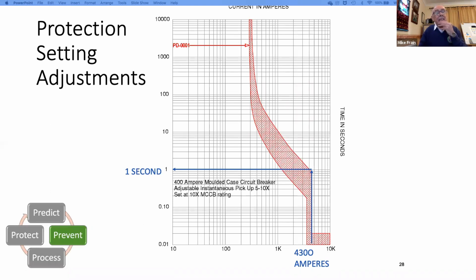I'm going to use a second example on that list I started with on prevent. In this case, I'm going to demonstrate the most commonly used technique for lowering the severity of an arc flash, and that is adjustment of upstream protective devices, certainly on low voltage systems. In this case, it's a protection curve for a commonly used 400 amp thermal magnetic circuit breaker, and you can see there it's got opening and clearing times on the same time current curve. So we're looking to the right-hand side basically to clear the fault.